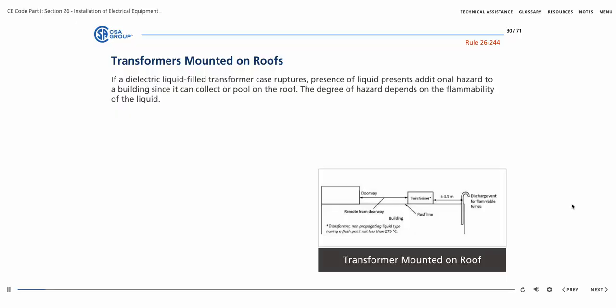If a dielectric liquid-filled transformer case ruptures, the presence of the liquid can present an additional hazard to the building since it can collect or pool on the roof. The degree of that hazard depends on the flammability of the liquid. Rule 26-244 establishes additional requirements for a dielectric liquid-filled transformer installed on the roof of a building. Appendix B, note to Rule 26-244, provides assistance in determining how the liquid in the transformer is to be classified.